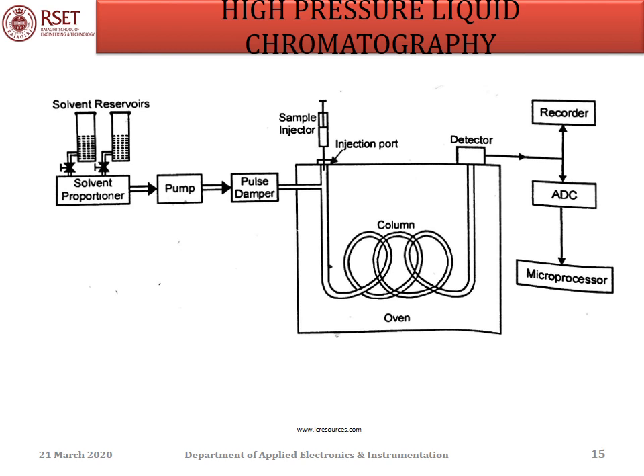High pressure liquid chromatography (HPLC) is the most widely used of all the analytical separation processes. The basic components of HPLC are: solvent reservoir for the mobile phase and its treatment; pumping system to force the liquid mobile phase through the column; sample injection system for introduction of sample into the mobile phase; chromatographic column with an appropriate length of stationary phase; detection system for detection of sample components as they elute from the column; and a microprocessor or recorder to provide a readable signal proportional to the amount of each component present in the analyte.